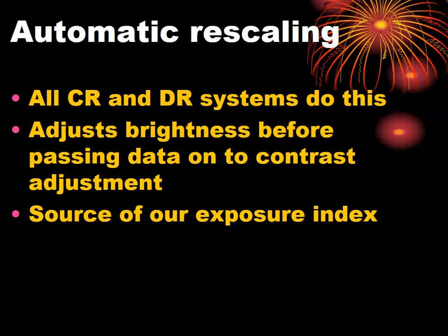All CR and DR systems perform automatic rescaling. The computer examines either the collimated region of interest or the whole panel, assesses how dark or light the image is, and adjusts it into a pleasing visual range — approximately 1.5 optical density units for humans. This preliminary adjustment either darkens or lightens the image for the user. This process is determined by the programmer's algorithm, and this is also where your exposure index value comes from.